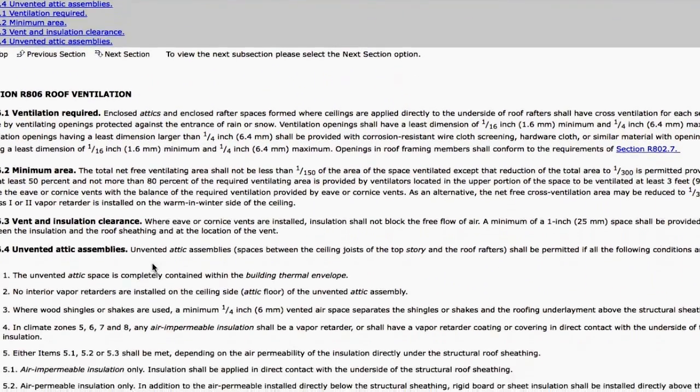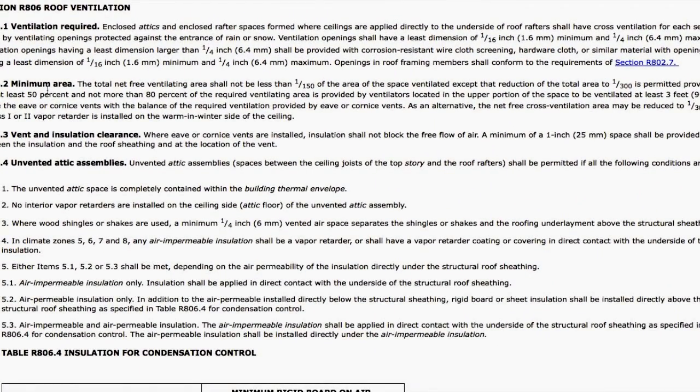Here's the code — this is a 2009 IRC code. As you can see there's not many lines in it but it goes into depth pretty well. Take the square footage of your attic space — not cubic footage, just square footage — and you want the ventilation to be 1/150th, which is the minimum you need.